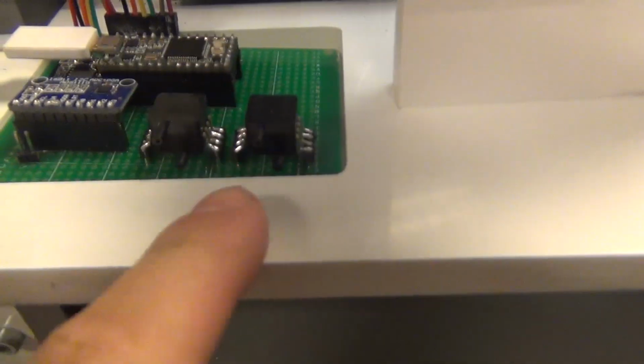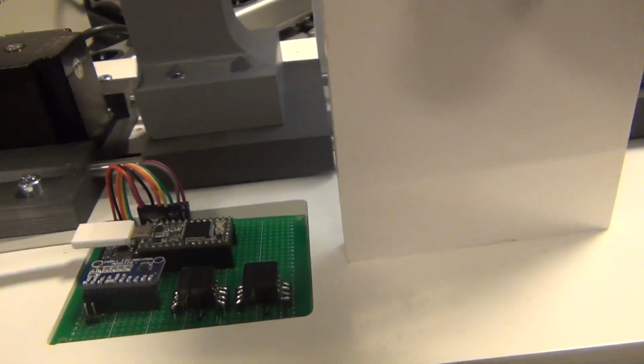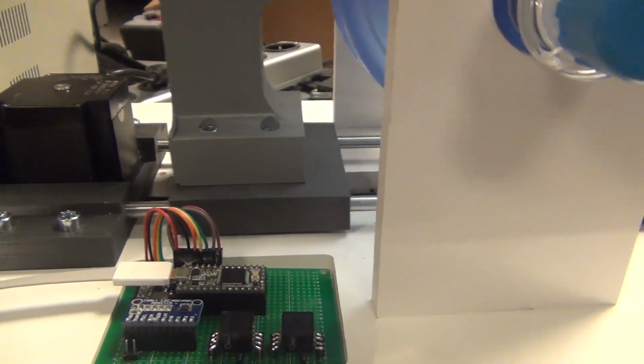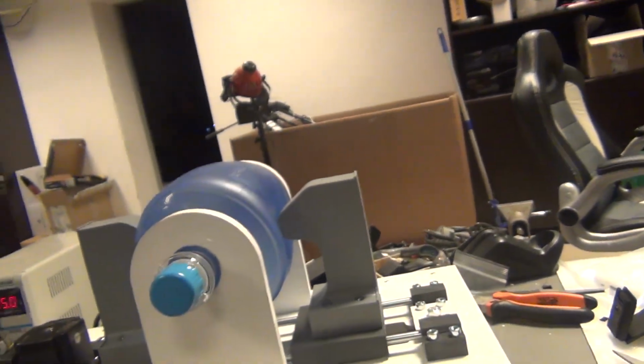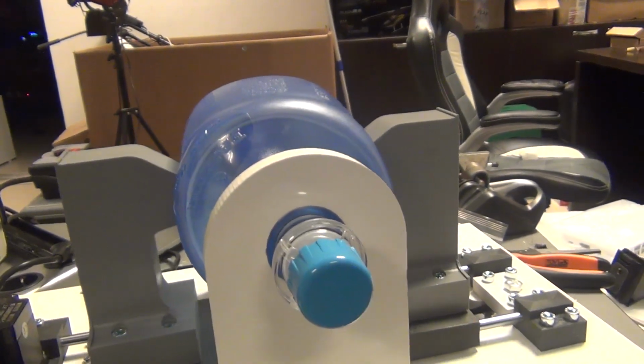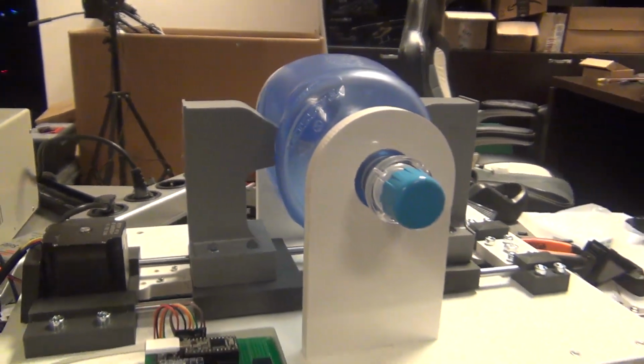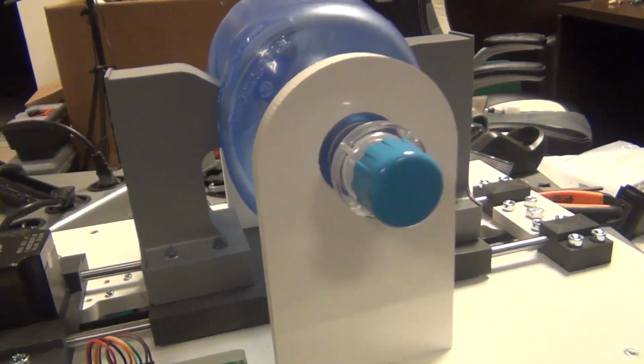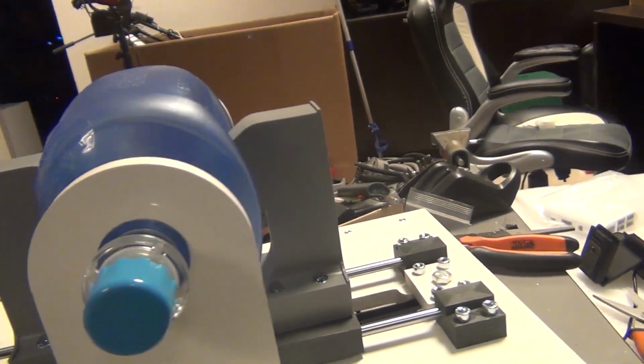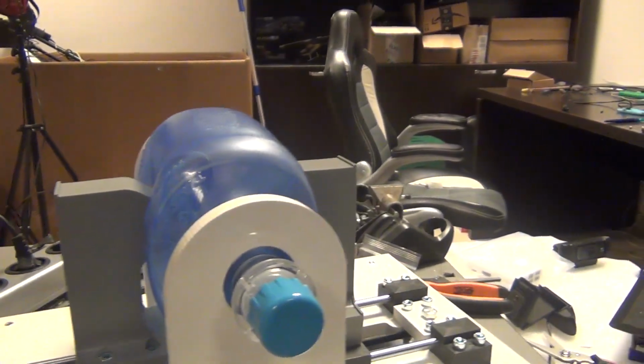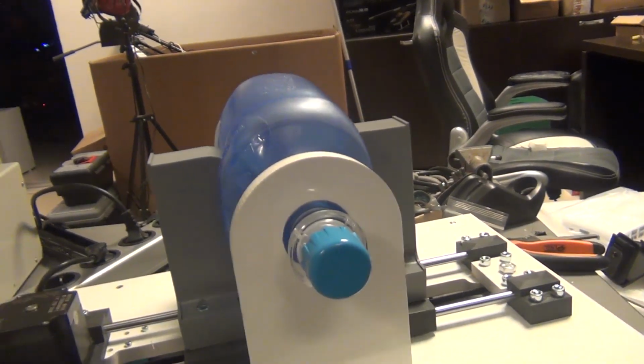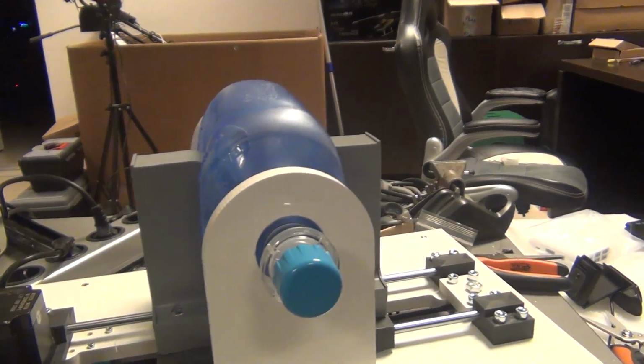So that's how it works. I checked a few videos on how mechanical ventilators work, and they explained all the settings and the modes that it should work in. And after we put these pressure sensors here, we'll get access to more advanced algorithms to support breathing, so when the user tries to inhale it can trigger the machine. It's going to get more advanced, but I hope if this is going to be useful for people, we'll get some more advanced programmers joining and implementing these algorithms, or finding a way to get access to some source code from other machines, so we don't have to test the algorithms and stuff like that.